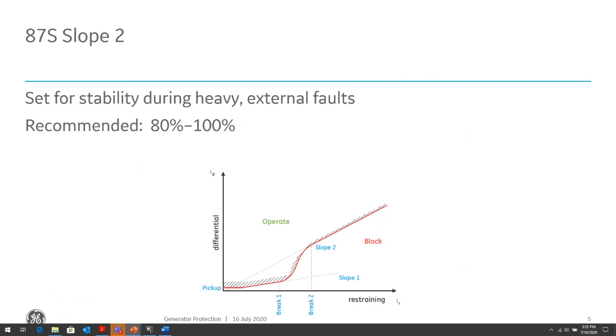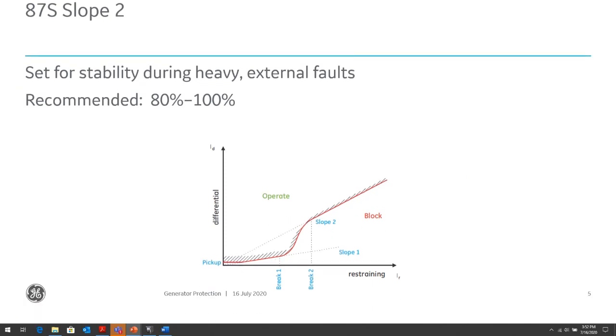So if you have a condition where you're going to see high saturation, then you want to set the slope pretty high. And we usually recommend 80 to 100%. That's close to some of the default settings, I think. And this is based on a lot of studies we've done for a lot of different fault conditions versus system conditions. So this is a very, very good compromise, if you don't have the ability to get all that information and do all of the calculation to determine exactly if your CT is saturating, and how much it is saturating.